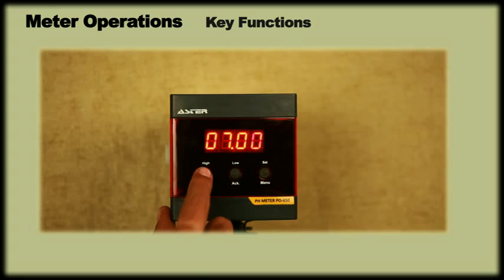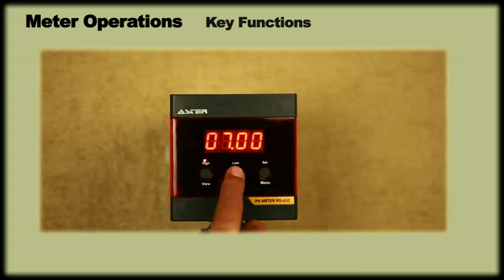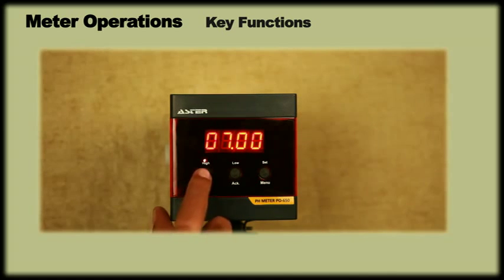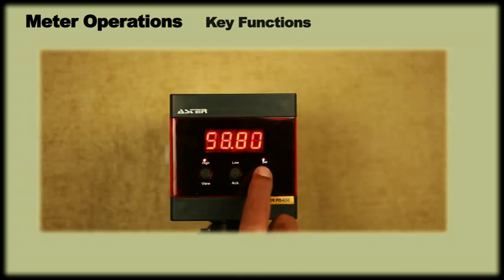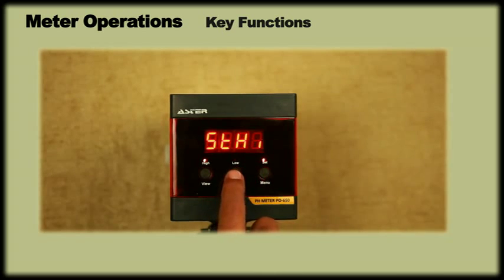The View key displays factory settings of relay like high on, high off, low on, low off, temperature, and output settings if any. The ACK key displays millivolt and resets the relay in case of fault. The menu key is used for high and low relay settings.